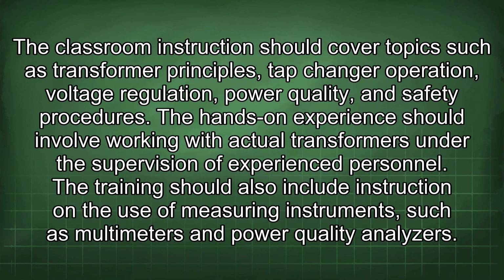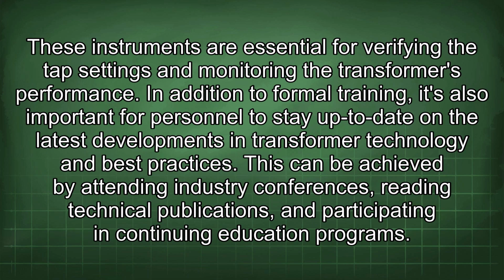The classroom instruction should cover topics such as transformer principles, tap changer operation, voltage regulation, power quality, and safety procedures. The hands-on experience should involve working with actual transformers under the supervision of experienced personnel. The training should also include instruction on the use of measuring instruments, such as multimeters and power quality analyzers. These instruments are essential for verifying the tap settings and monitoring the transformer's performance.